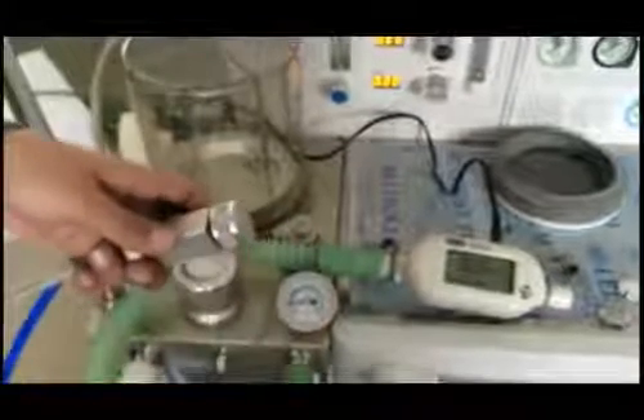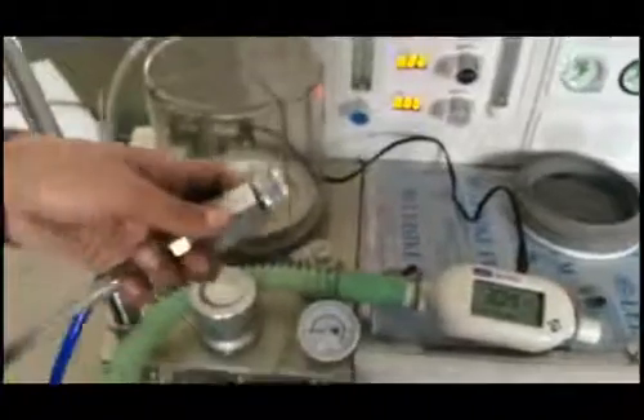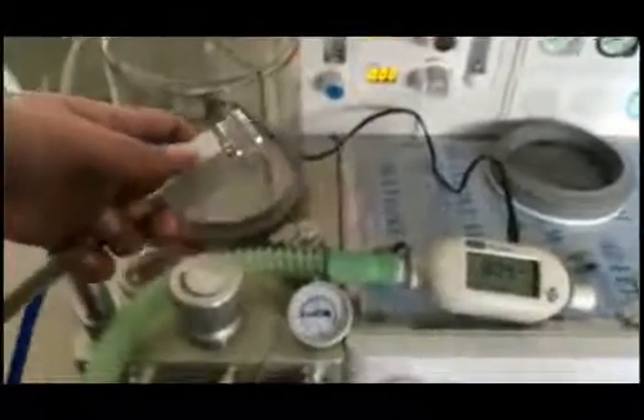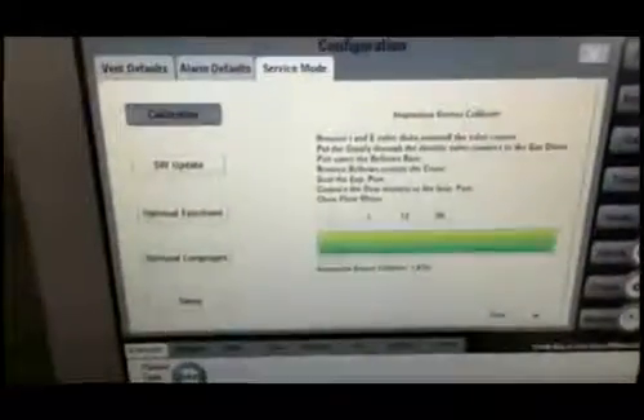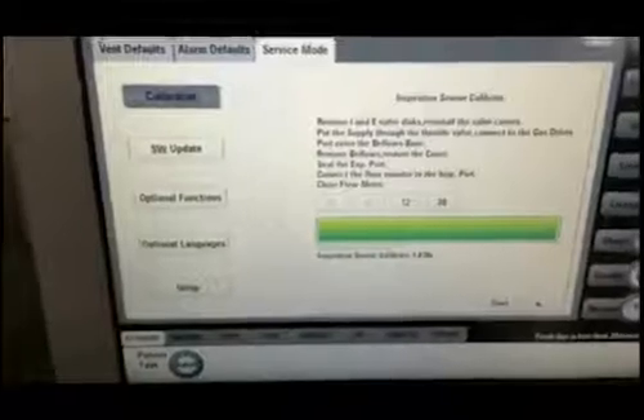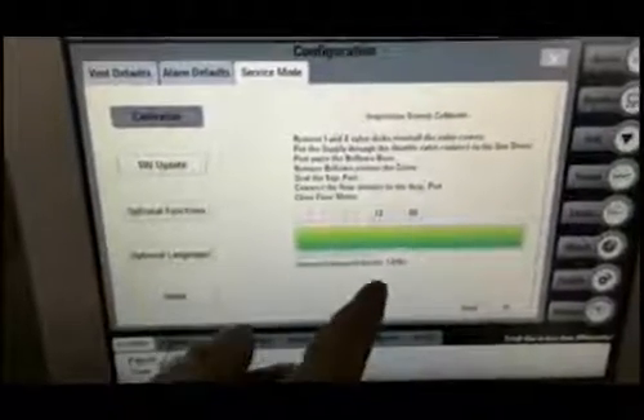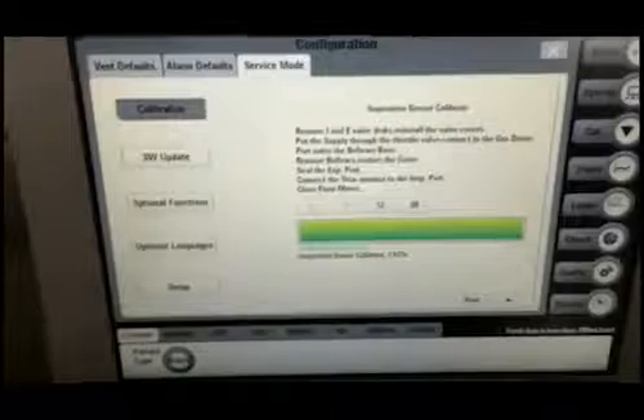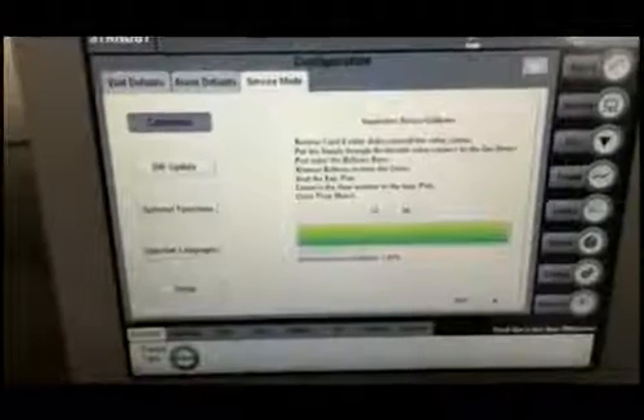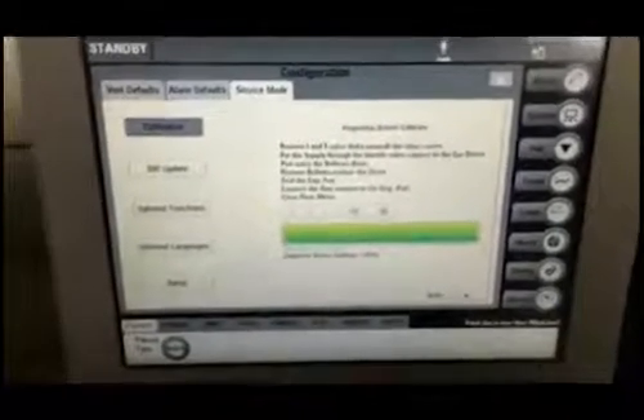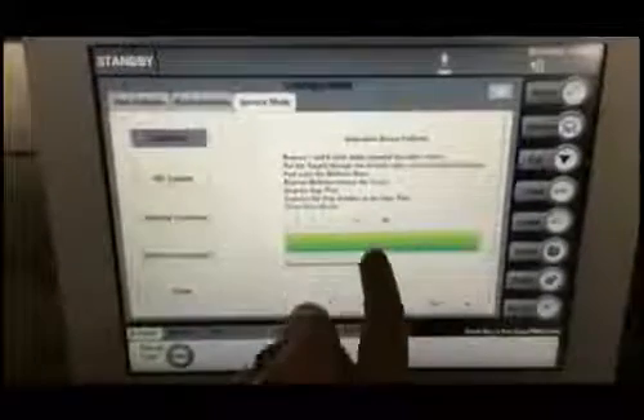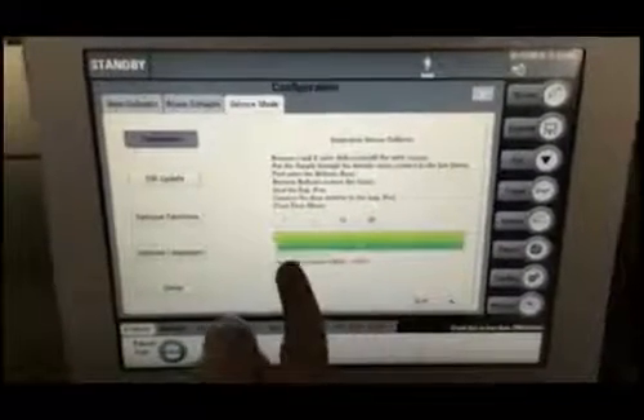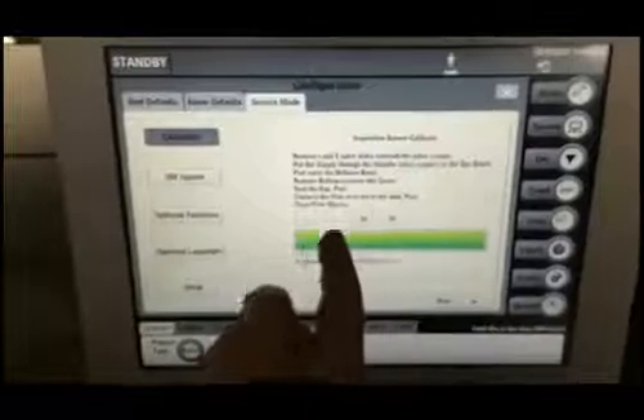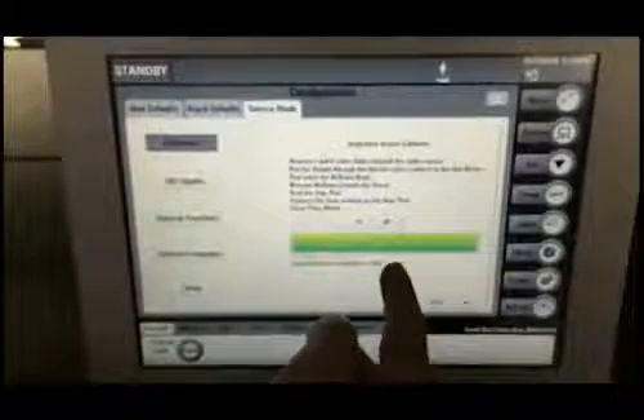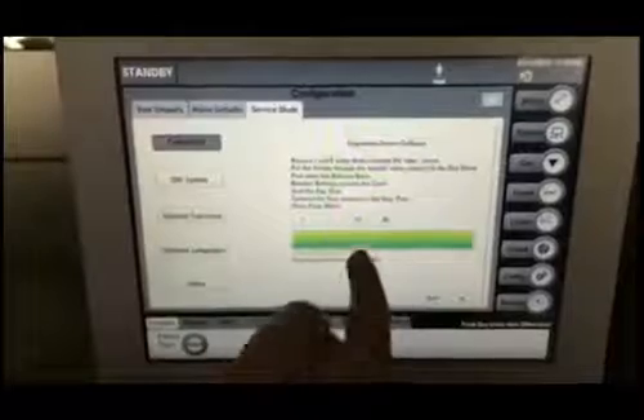As you can see, the flow meter has arrived at 3. Please wait for a few moments and then press the key on the screen. After pressing the key, a calibration successful sound will be displayed. Please remember, you have to perform the calibration in order 0, 3, 12 and 30. You cannot perform 12 before 3 or in this order, and you have to perform all 4 calibrations.